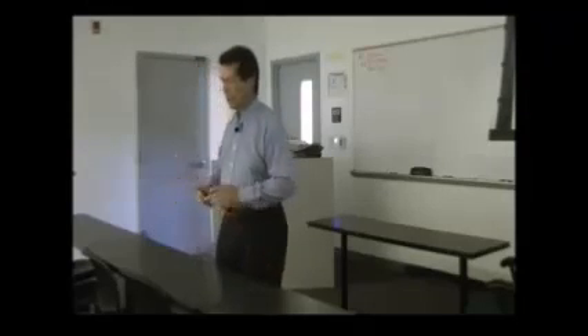Now all this will be designed. Your mechanical engineering consultant firm will design and size the cooling towers. Our job in regards to maintaining them is, again, accessibility. Can I get to the sumps? Can I get to the media? Do I have sand filters? Do I have water pressure? We saw a pump that they were using in the combined heat facility. Is my piping labeled? Are my strainers easy to get to? Or do I have to stand on a ladder to get to the strainers? So those are some considerations to think about.